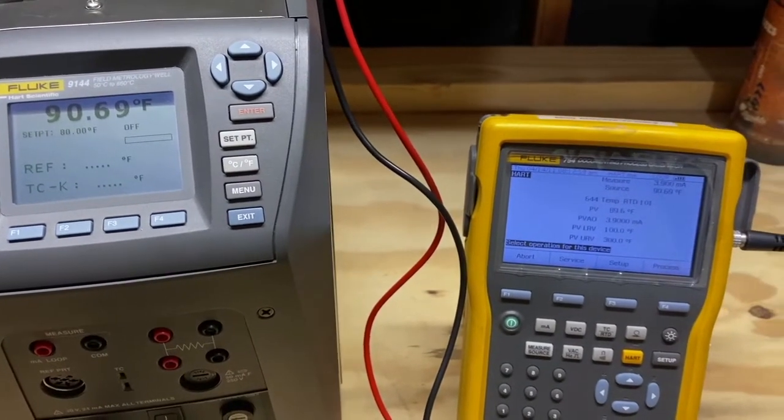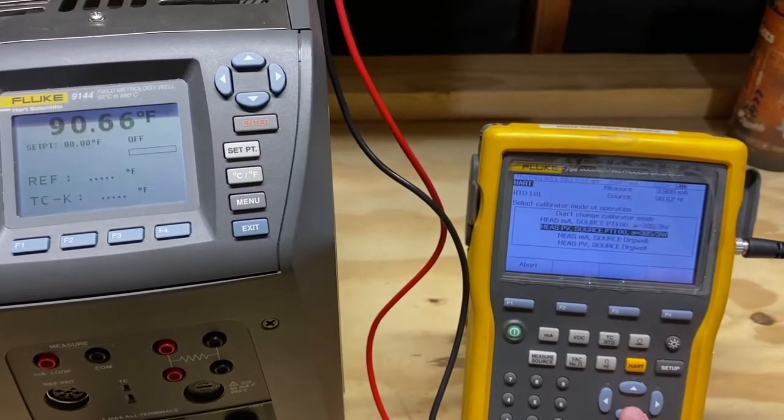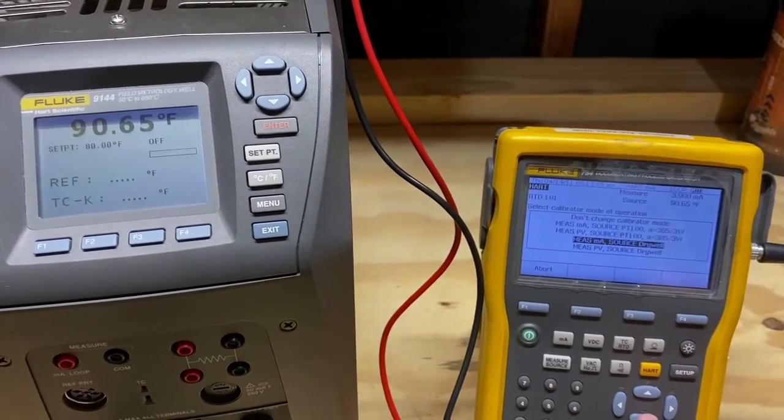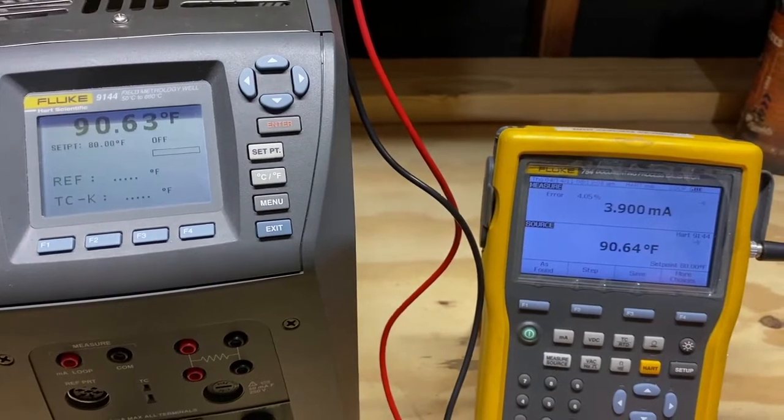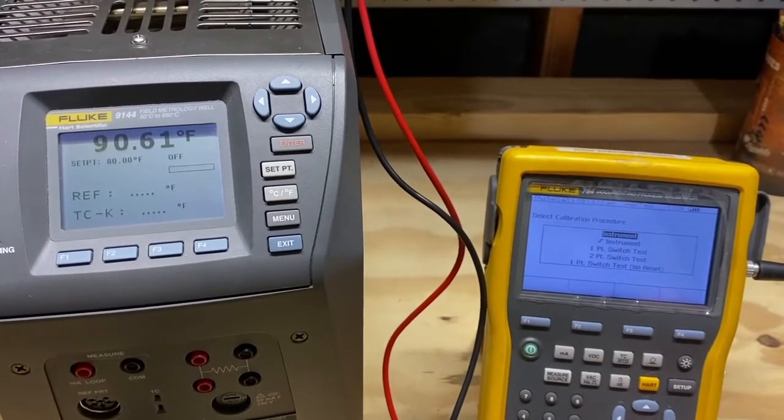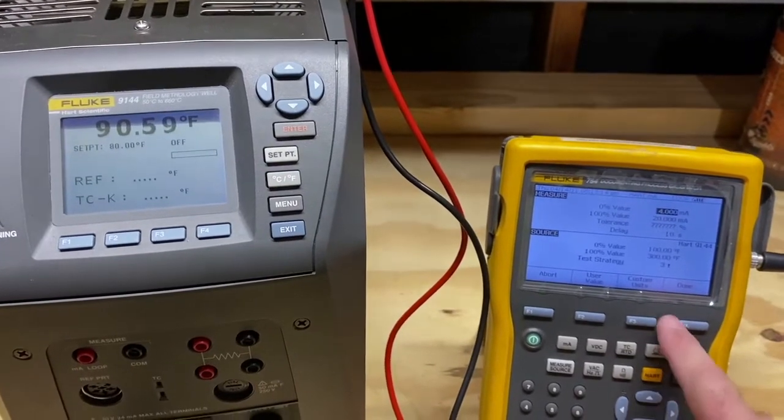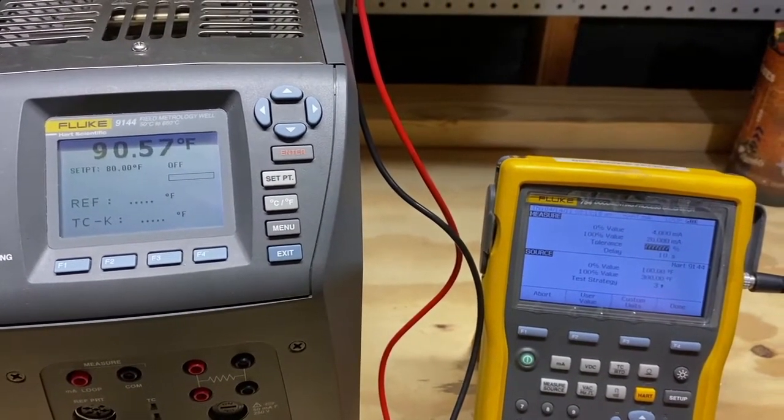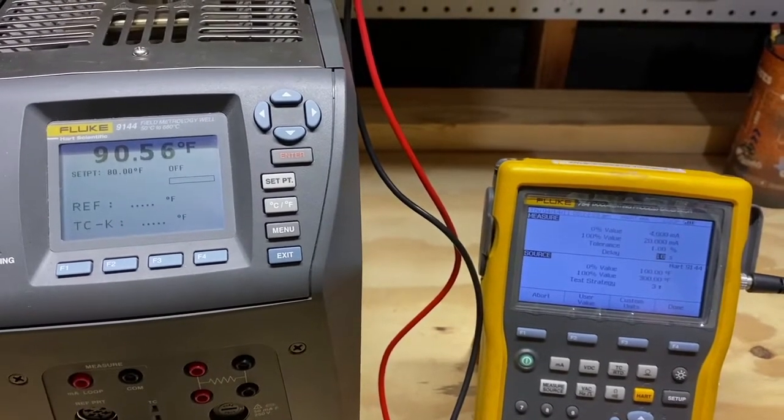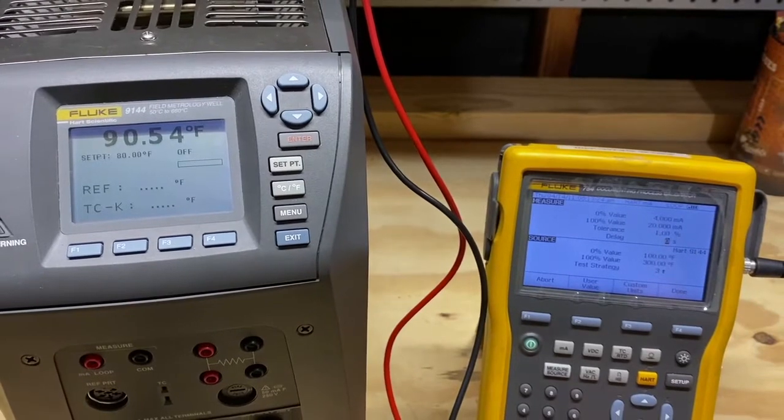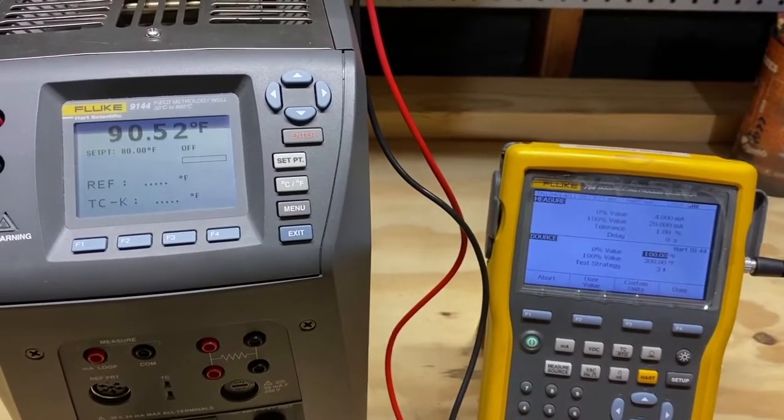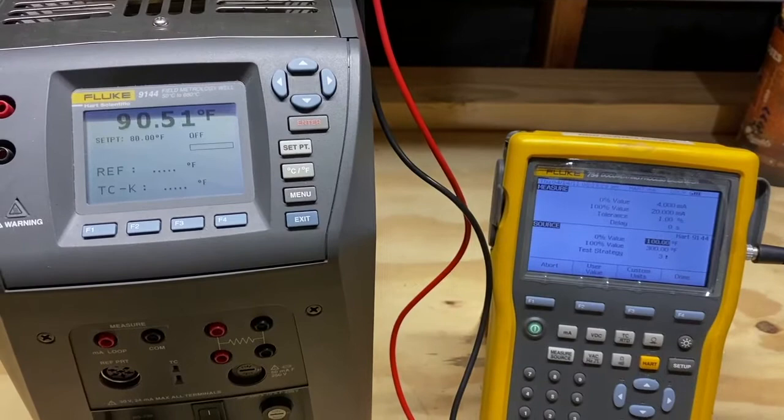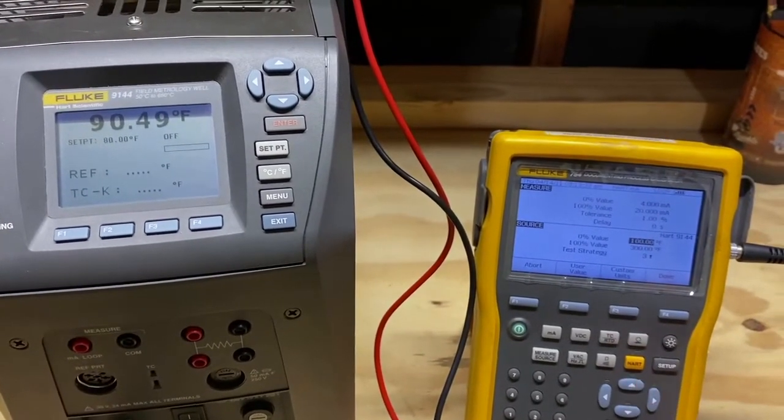To begin the calibration, we will hit the measure source button. We will select that we want to measure milliamps but source with the dry well. Select as found, select instrument calibration. It is a 4-20 milliamp calibration. We are going to select 1% tolerance. We are going to select 0 seconds on the delay. This allows the dry well to dictate when the next point is incremented once it comes to proper temperature and settles.